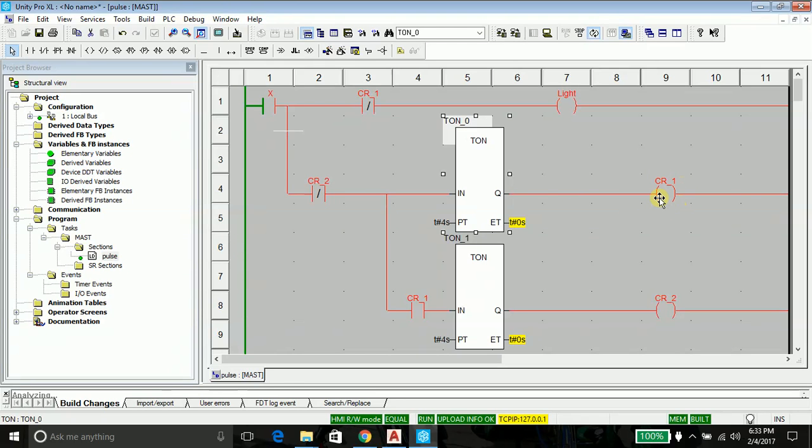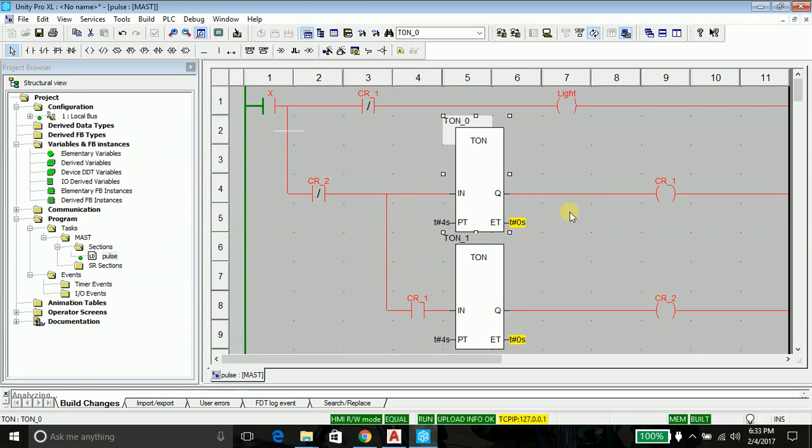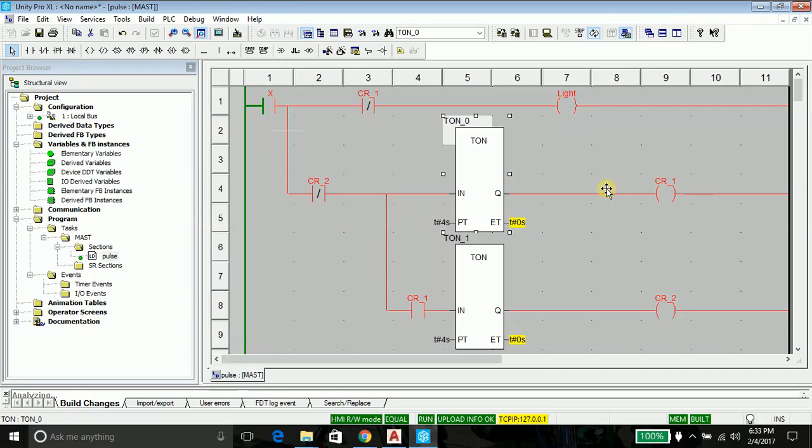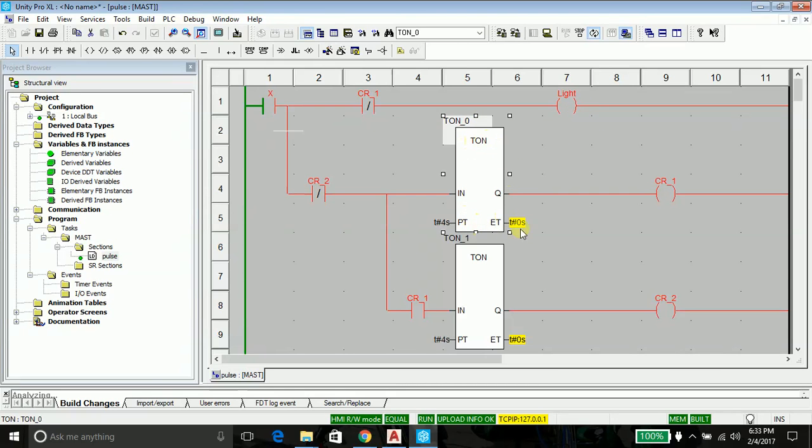And this timer will produce the output, that means it will energize this coil after two seconds—though it says four seconds, it's just to show you because everything happens quite fast. I can't discuss the things, so observe this. When this contact is energized, what will happen is that this contact, which is a normally closed contact, will become open and my light will switch off. So this timer is recording the on time, so it is switching off the light.